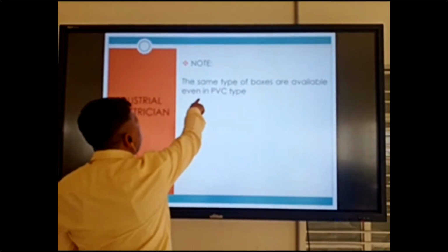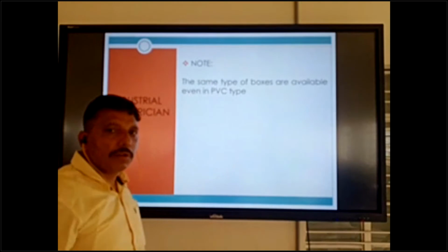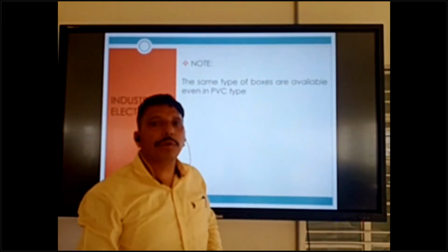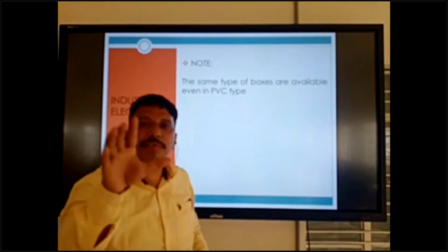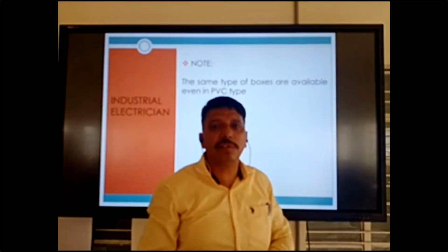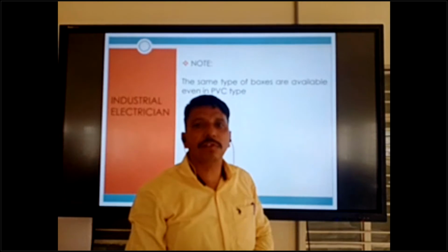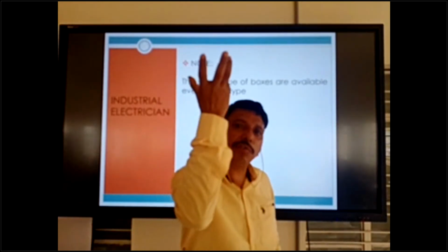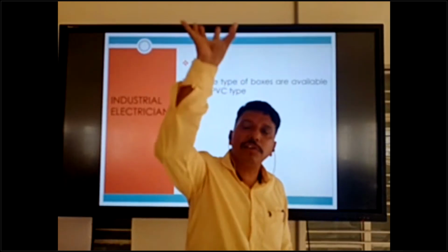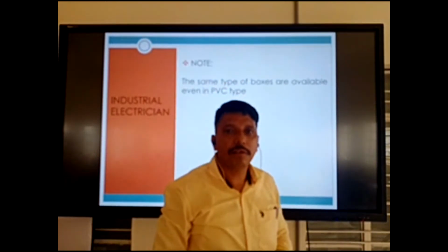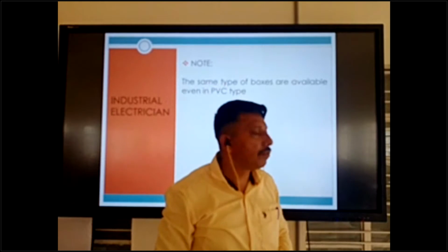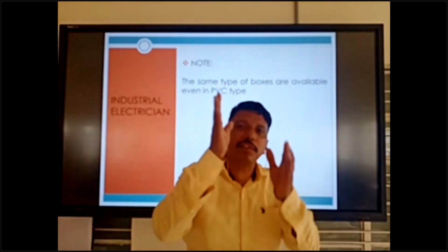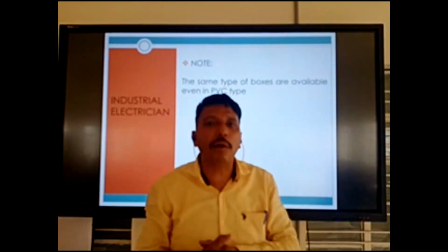These same types of boxes are available in PVC types also. But we cannot use 3/3 and 3/6 PVC boxes in most cases. This is not allowed. Only circular box we can use in PVC in concealed wiring, but 3x6 and 3x3 PVC box is not allowed.